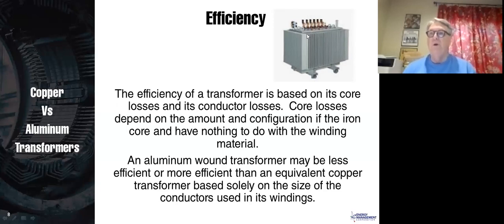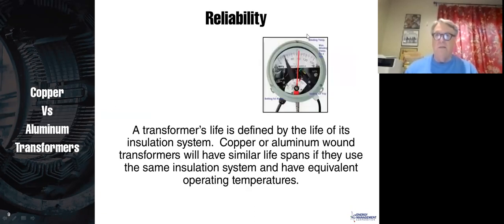And then a transformer manufacturer will optimize their transformer design in order to come up with the best transformer that's going to evaluate the best in your evaluation. Turns out that doesn't really have a lot to do with aluminum or copper. You can make the aluminum conductors bigger, or you can make the copper conductors bigger. You can make both have equivalent efficiencies. So basically, I would say this is sixes.